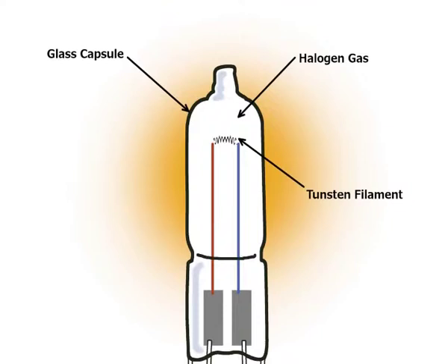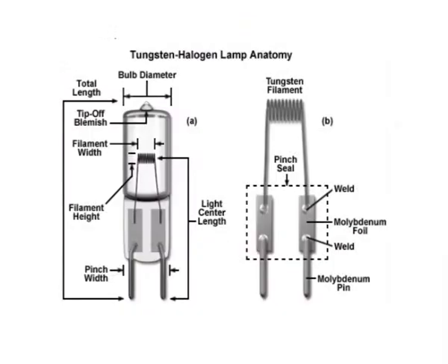Tungsten halogen lamp. It is the most common light source used in the spectrophotometer. This lamp consists of a tungsten filament enclosed in a glass envelope with a wavelength range of about 330 to 900 nanometer, used for the visible region. Due to evaporation of tungsten, life period decreases, which is overcome by using tungsten halogen lamp.